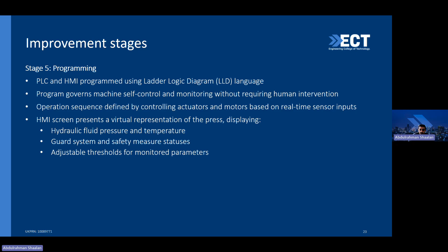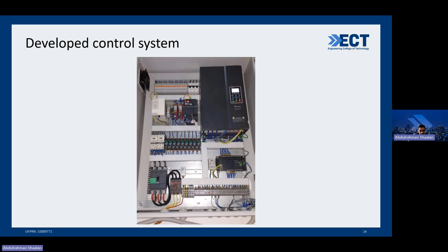This was the control panel that was developed in order to control the machine. We used a Schneider PLC and VFD to control the main motor and all the different relays to control the different parts. We used safety relays and all the circuit breakers related to the machinery, and we had the main circuit breaker, plus all the different terminal blocks that connect all the parts and components to the distribution of the control panel.